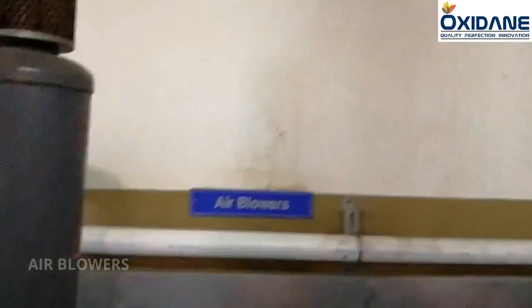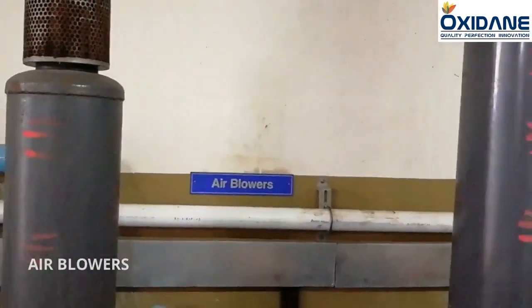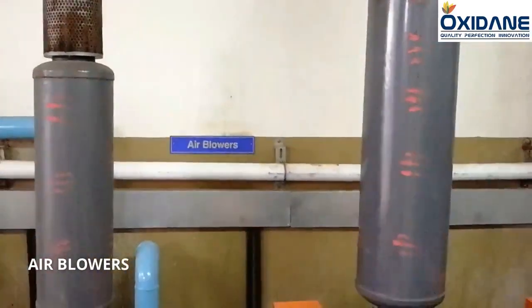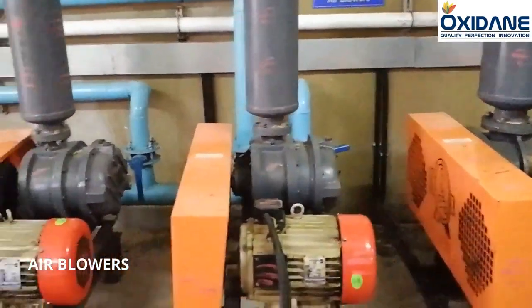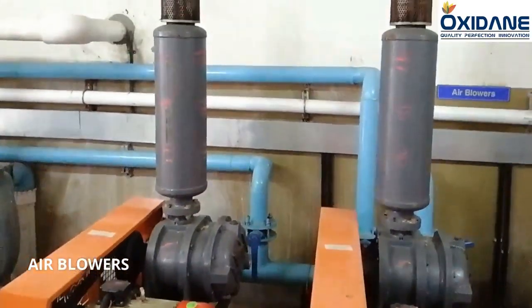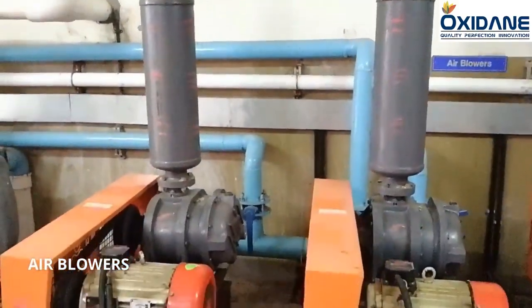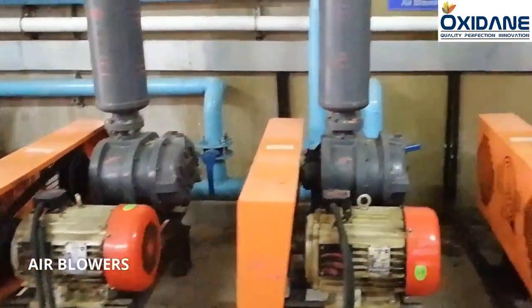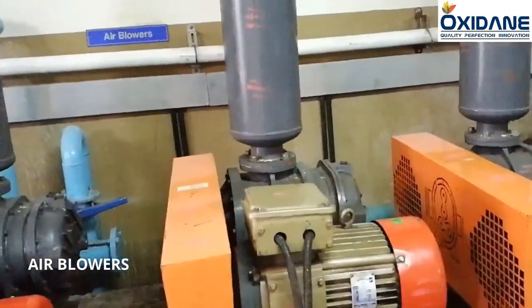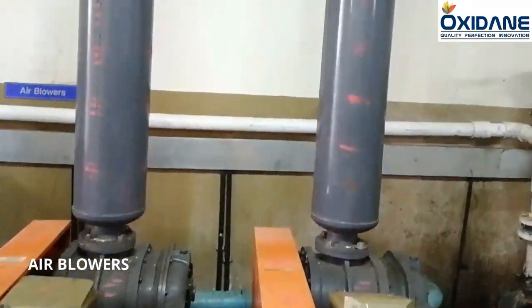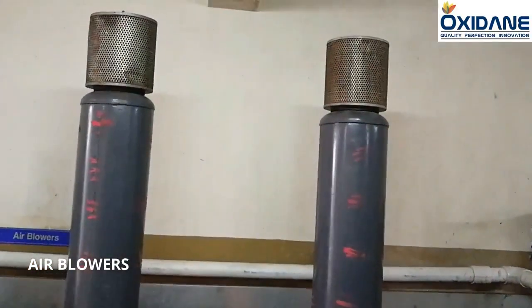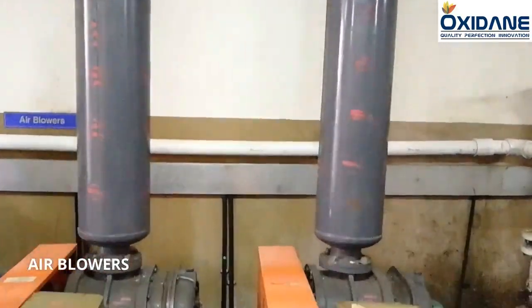Air blowers. Proper aeration and blower selection are two of the most important considerations at a wastewater plant. Here in the plant there are 4 air blowers, divided in pairs of 2, where one air blower acts as a standby when the other is in operation. This is done to reduce the load of work for one air blower by switching between them at different intervals of time. This ensures continuous operation of blowers throughout the treatment process.